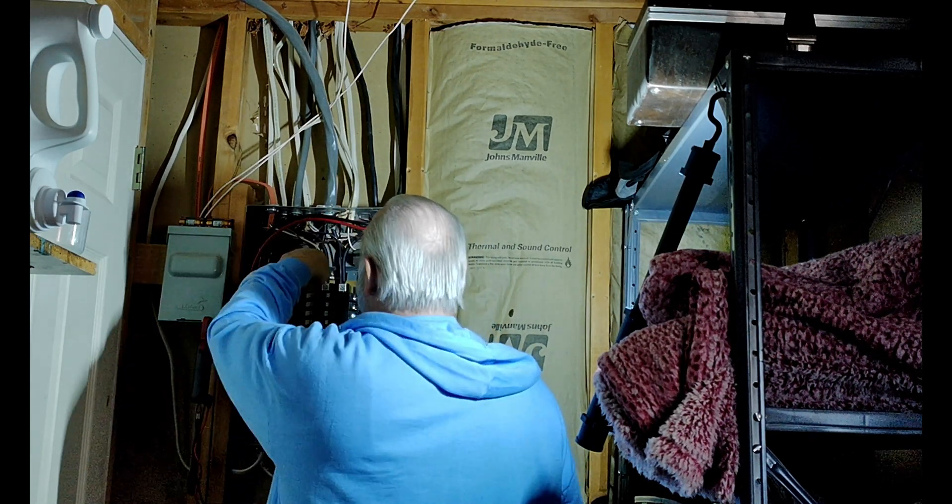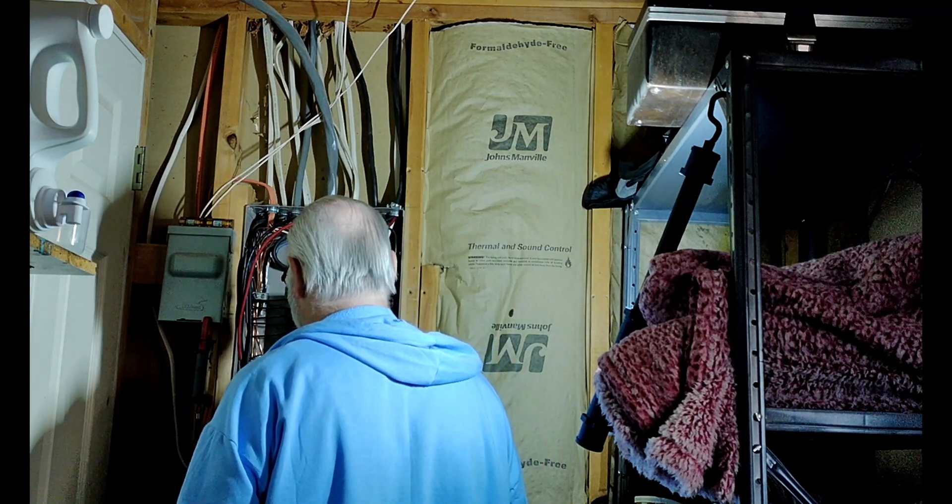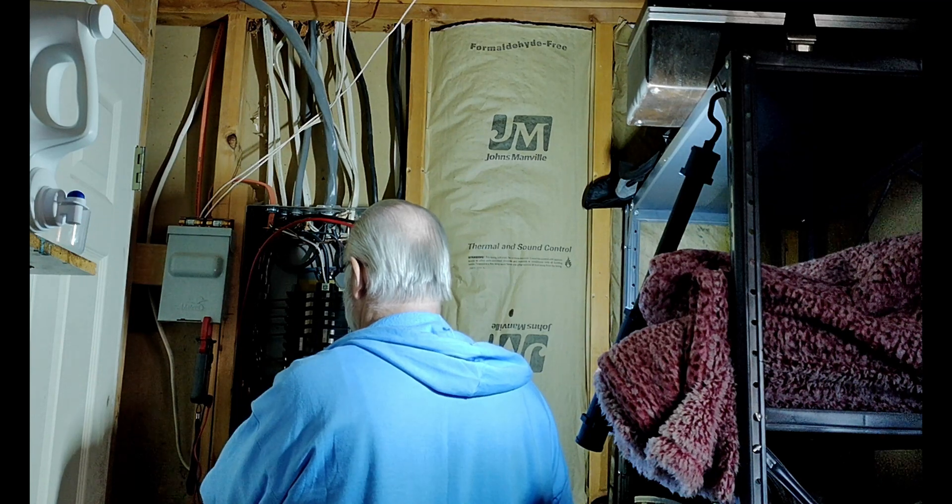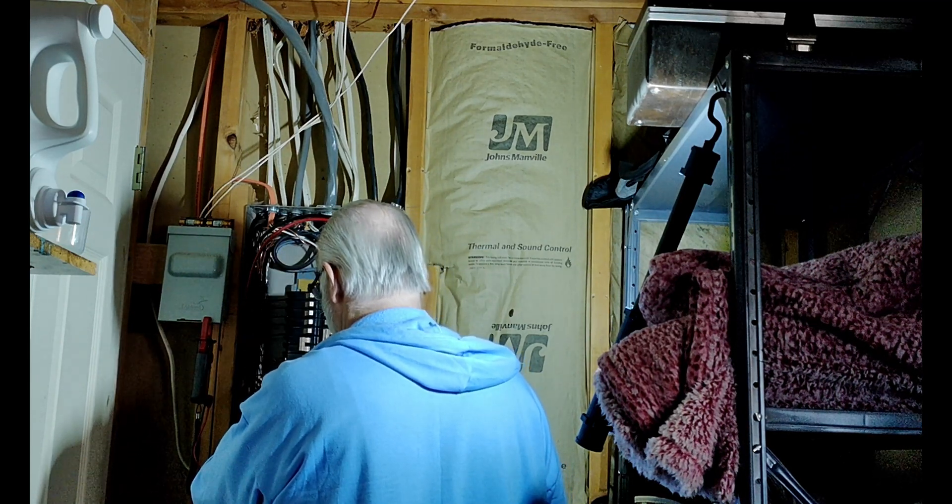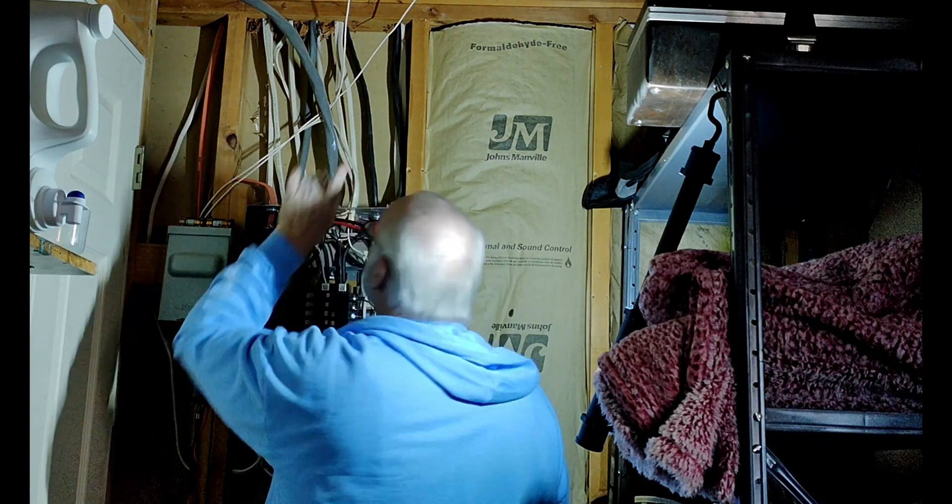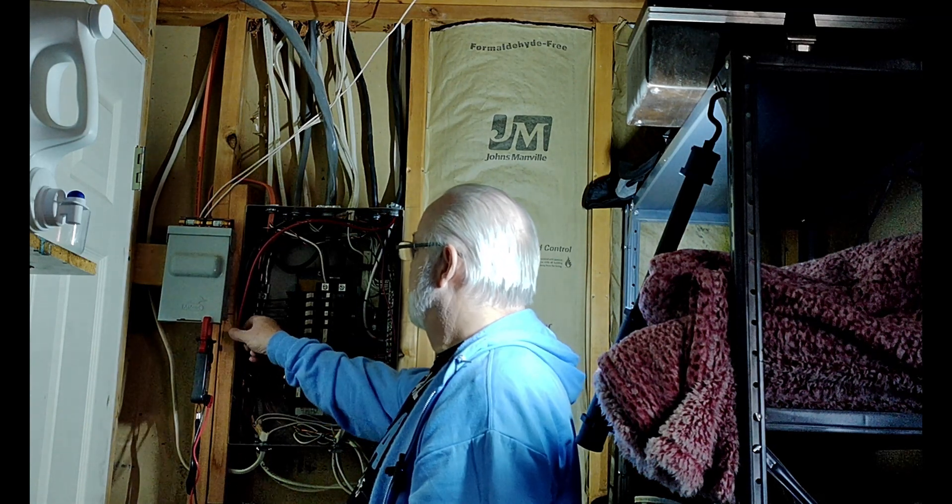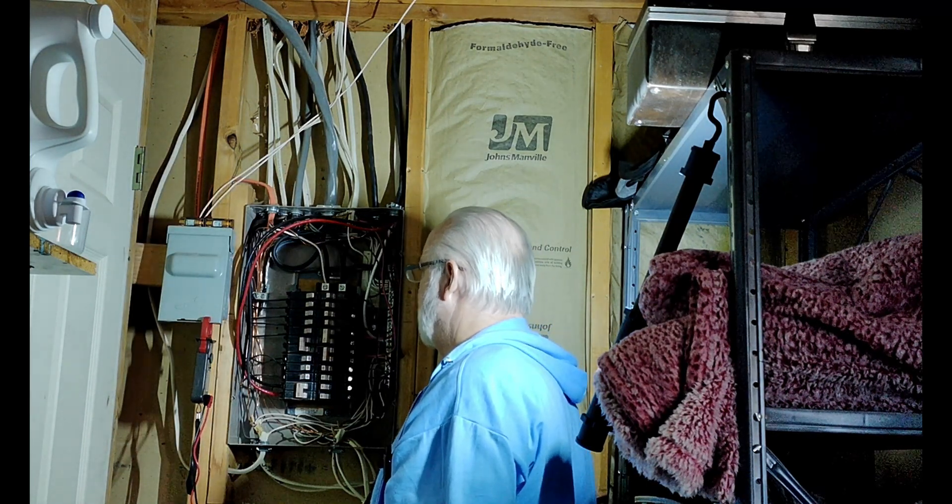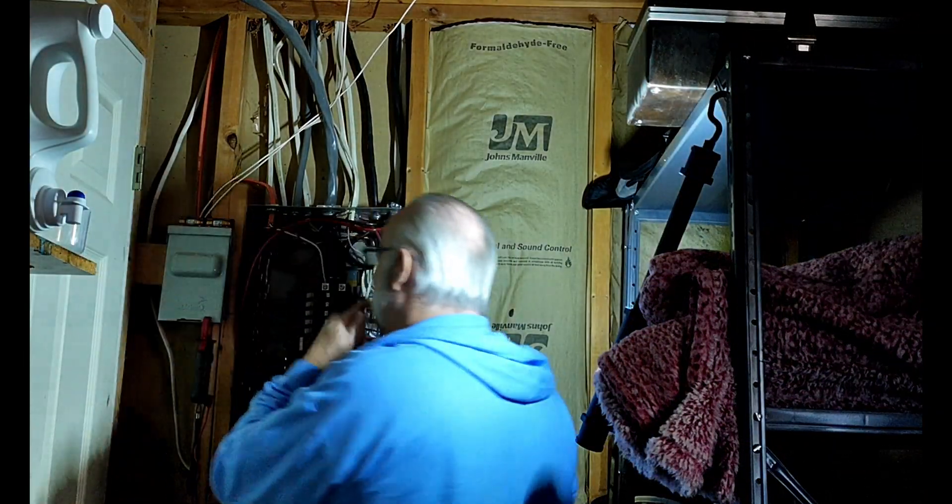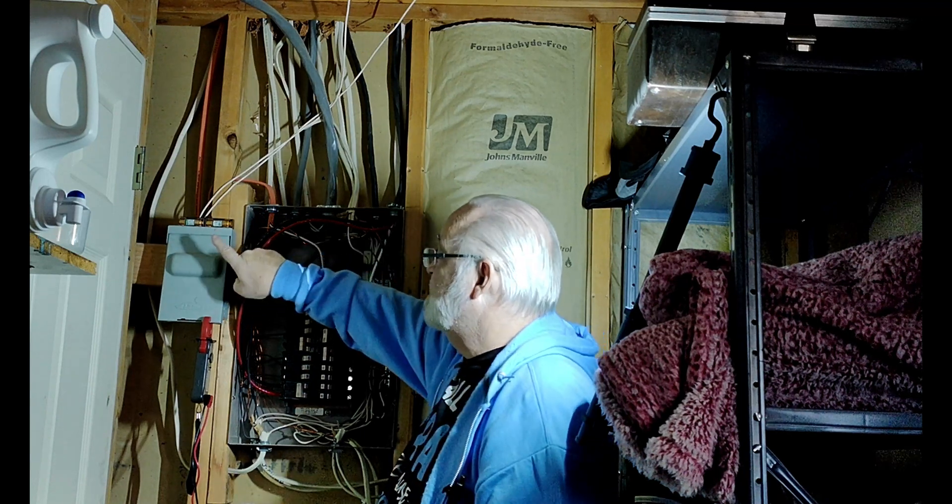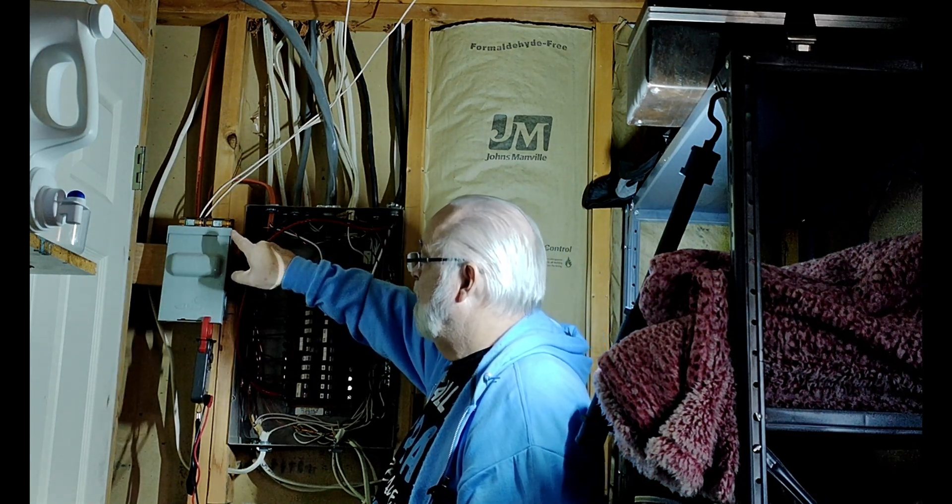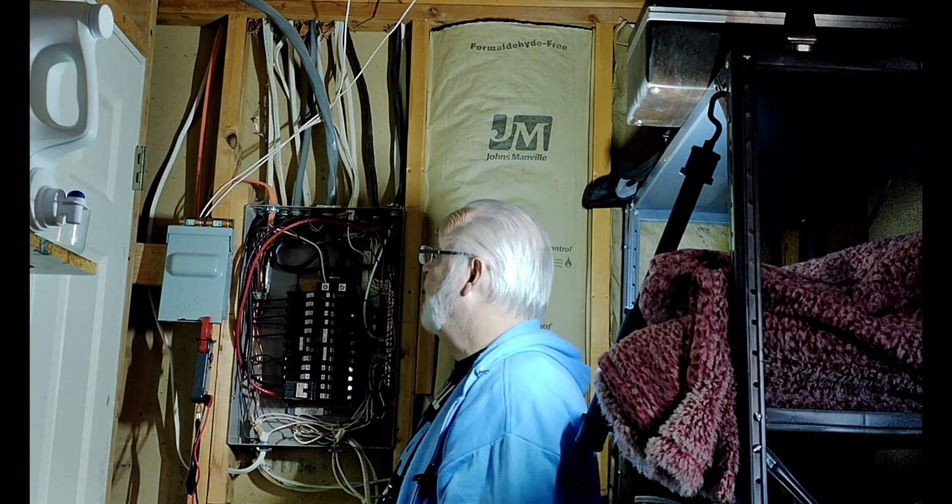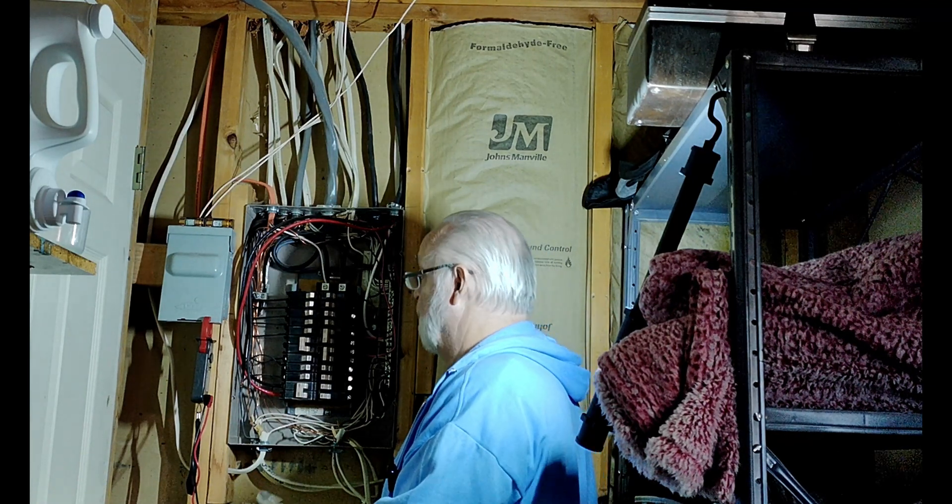First thing we want to do is remove these two lines because those should not be hooked up like that. That's just nuts. This in itself is a safety risk because if something ever happened and the AC overloaded and those fuses didn't blow, 100 amps of circuit would be ripping through that thing, starting a fire. Whoever did this should be ashamed of themselves. This is just not the way you do things. So always, I always double check my lines to make sure there is no power.